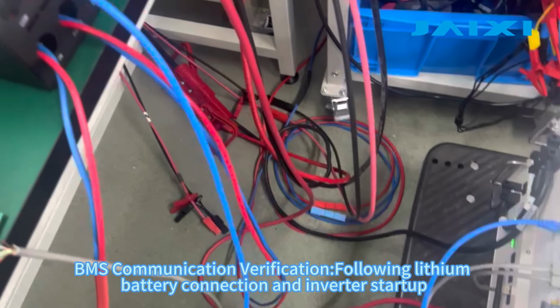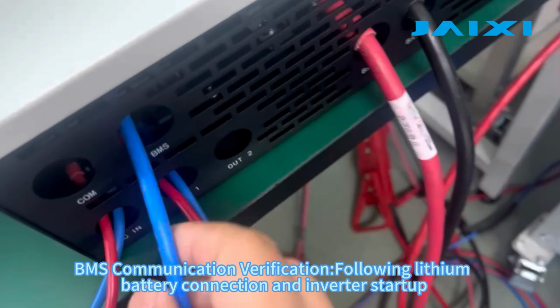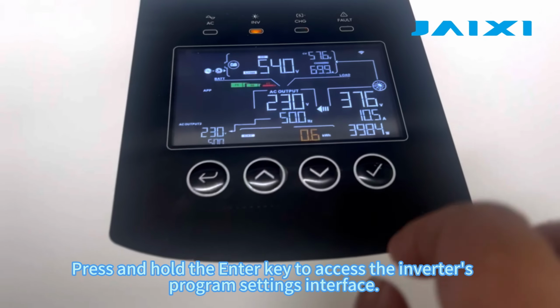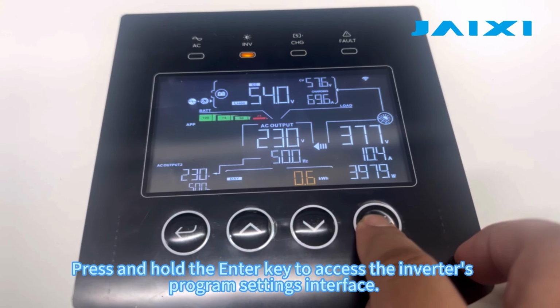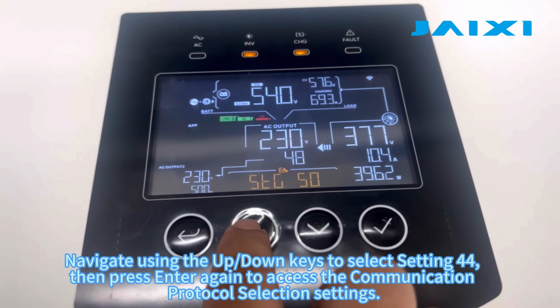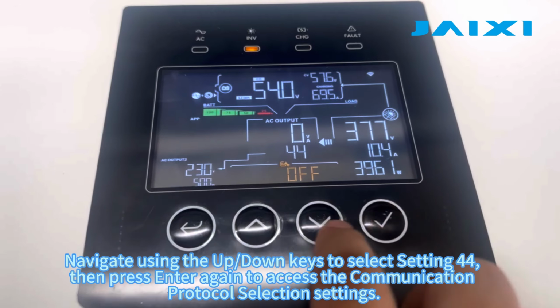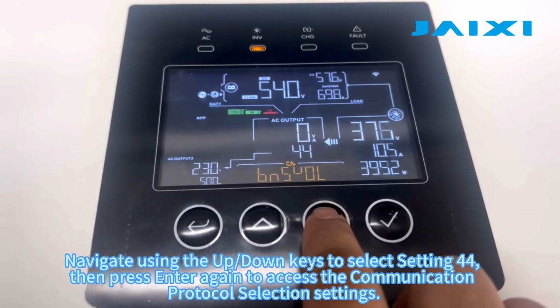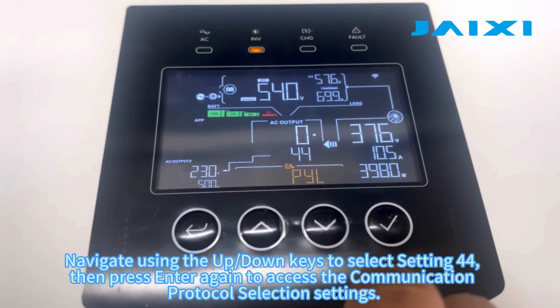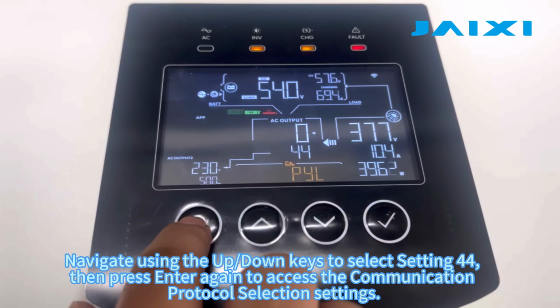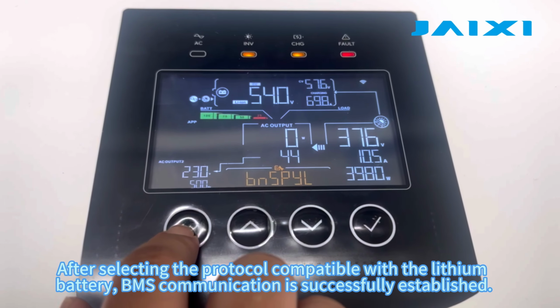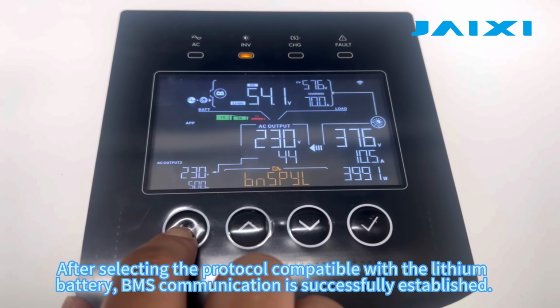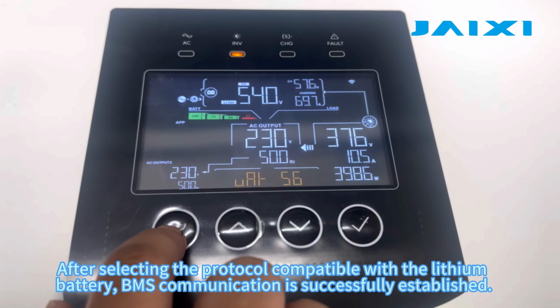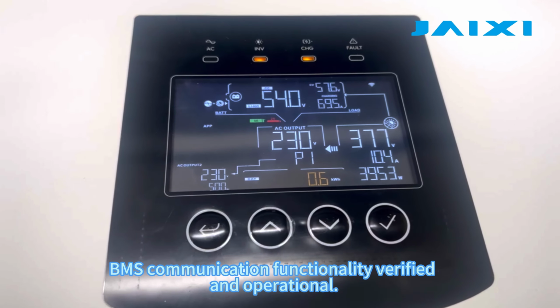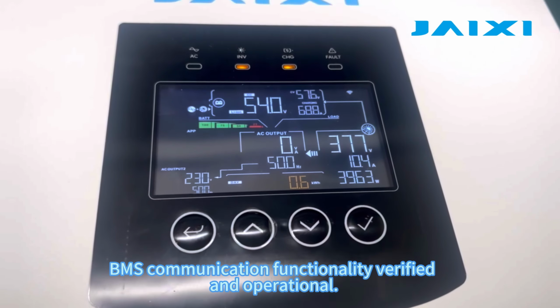BMS communication verification. Following lithium battery connection and inverter startup, press and hold the Enter key to access the inverter's program settings interface. Navigate using the up-down keys to select setting 44. Then press Enter again to access the communication protocol selection settings. After selecting the protocol compatible with the lithium battery, BMS communication is successfully established. BMS communication functionality verified and operational.